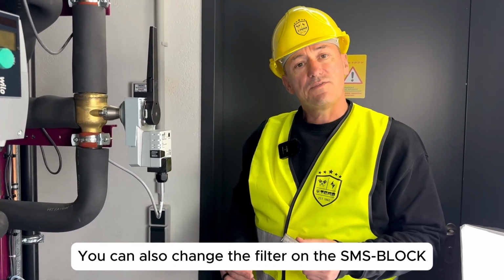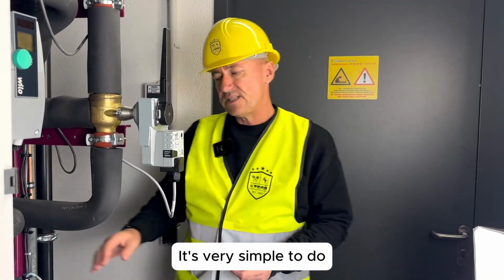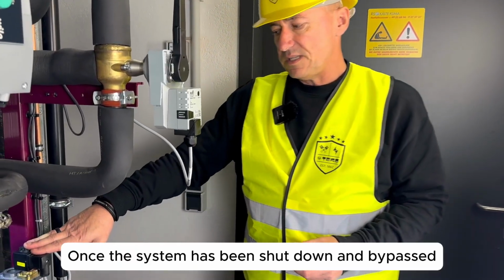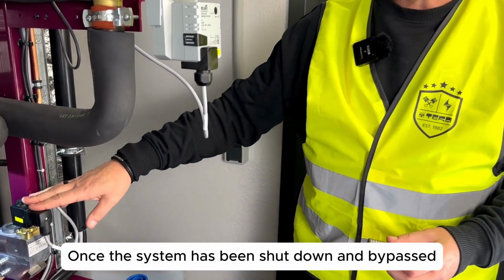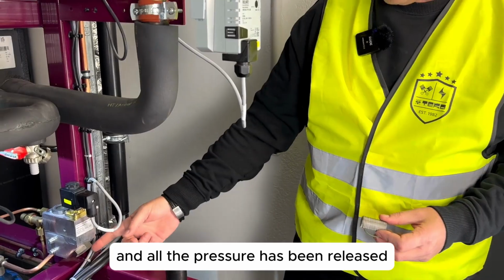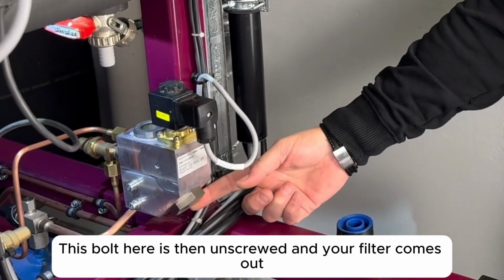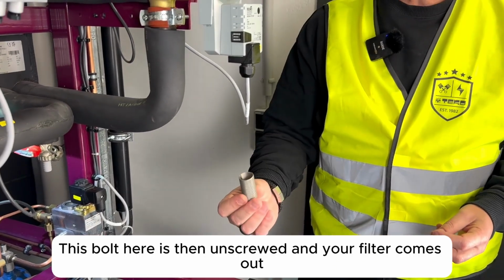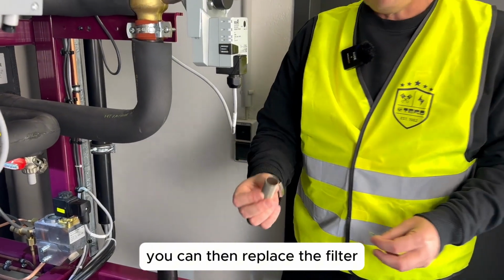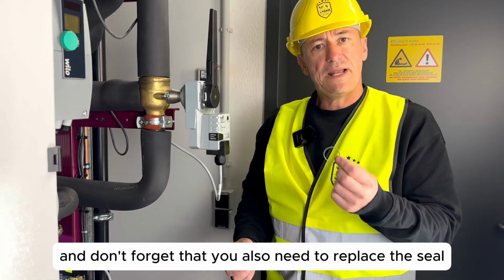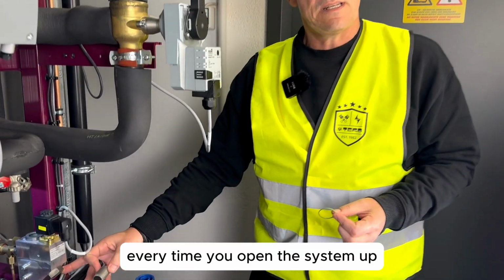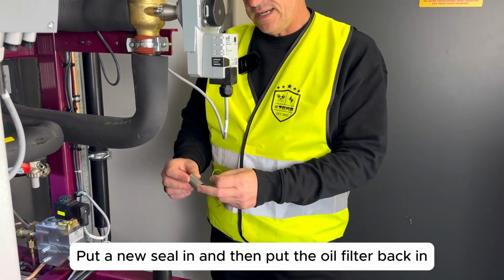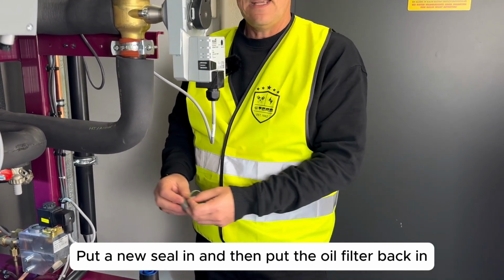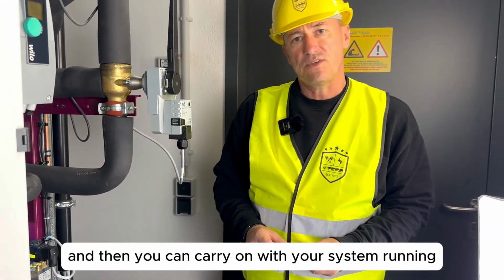You can also change the filter on the SMS block. It's very simple to do. Once the system has been shut down and bypassed and all the pressure has been released, this bolt here is then unscrewed and your filter comes out. You can then replace the filter, and don't forget that you also need to replace the seal every time you open the system up. Put a new seal in and then put the oil filter back in, and then you can carry on with your system running.